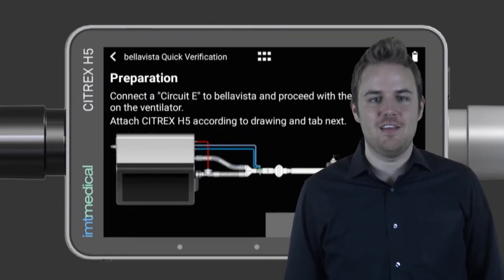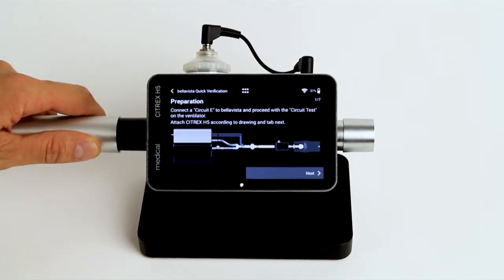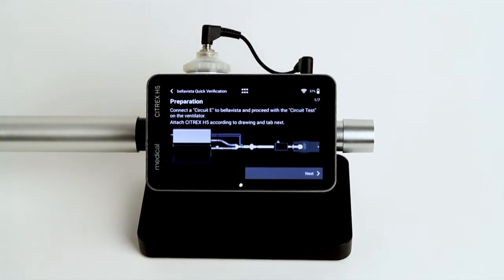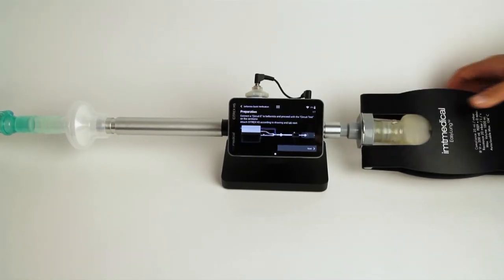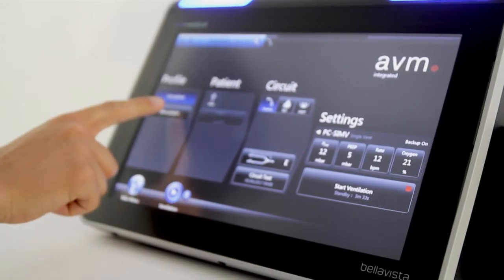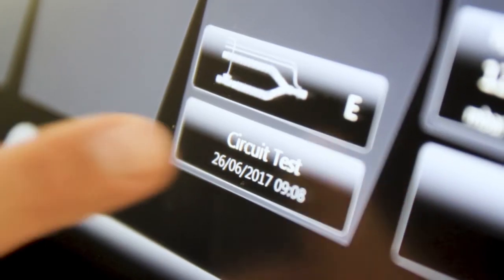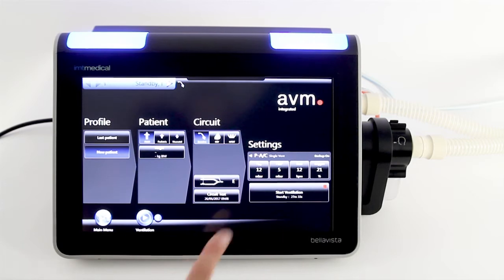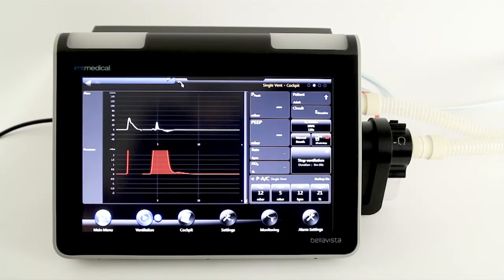Connect a bellavista ventilator to the CITREX H5 gas flow analyzer according to the diagram. Ensure that a successful patient circuit test has been performed before. Now start ventilation with default settings and wait for at least 10 breaths to be applied to the system.